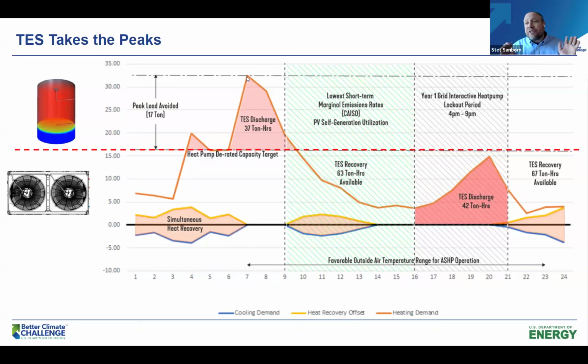That is very typical for a commercial building. And that peak tends to occur with what we call morning warm up. So that's when somebody said, hey, at 6 a.m., we need to turn this building on so it's ready for the first folks that come in so they don't complain. We don't want any complaints. Well, you're spending a lot of money for that 3-hour period. And something that we would prefer to do is spend the money on a smaller heat pump and let the thermal energy storage tank carry those 3 to 4 hours to help meet that peak.